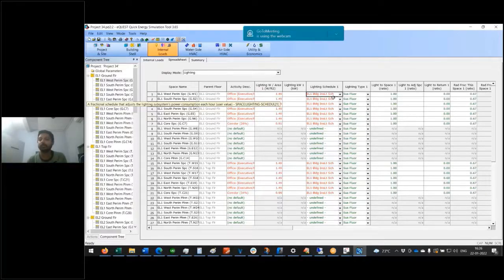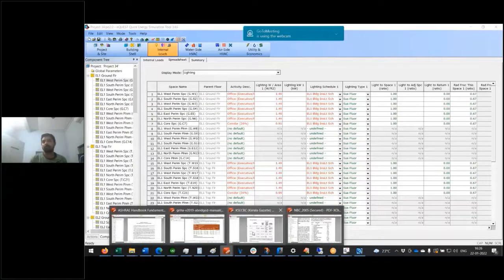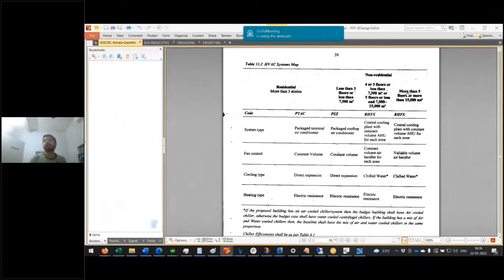In the previous case, though the number of floors is more, the area is only 3000 square meters. That does not matter. The rule is a rule. It's clearly mentioned: if it's more than 5 floors or more than 15,000 square meters, either one of these, then you have to go for centralized cooling. And in any case, centralized cooling will give you more energy consumption. So in the proposed case, you will in any case be achieving savings. So why are you even worried?